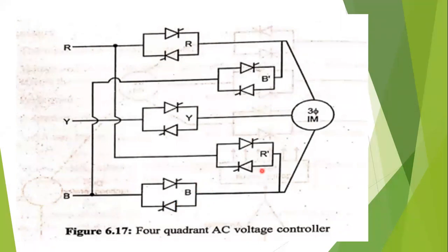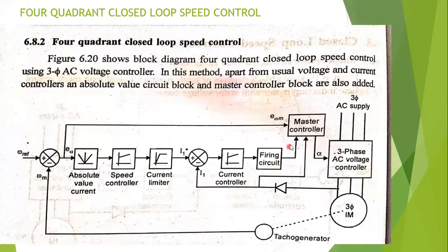And also here the master controller provides a delay of approximately 5 to 10 milliseconds after zero current is sensed, for ensuring that the outgoing SCRs are turned off.